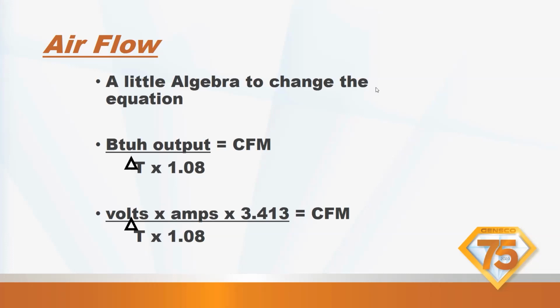For an electric furnace, you're going to take the volts. So you're going to measure the voltage coming in times the amps. You're going to average the volts between the breakers, and then you're going to add up the amps. So if you have 4 elements in there and you've got 2 sets of breakers, you're going to add up the amps for both breakers. Okay, times that by 3.413. That's the BTU value, and then we're going to get CFM. Okay, volts times amps times 3.413 divided by the delta T times the specific gravity, and that's going to give us CFM.